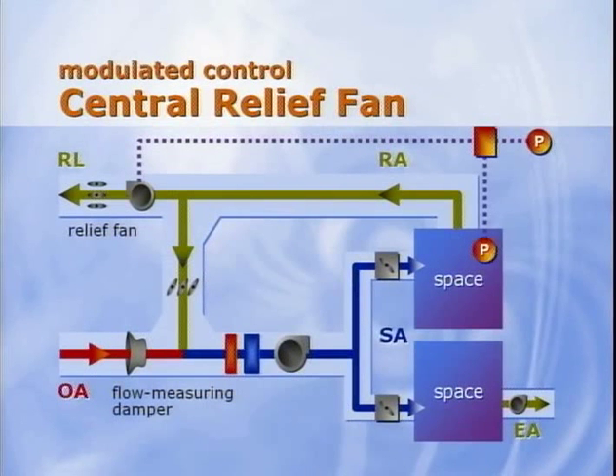One of its drawbacks is that it is always on and must always be controlled. Now let's look at a relief fan. In the relief fan configuration, the fan is located outside of the ventilation loop and only needs to operate when it is necessary to relieve excess building pressure. In some applications, when the rooftop unit is bringing in minimum ventilation airflow, local exhaust fans in the restrooms and exfiltration due to building pressurization may be sufficient to relieve all the air brought into the building for ventilation. In this case, no centralized relief is needed and the relief fan can be turned off.